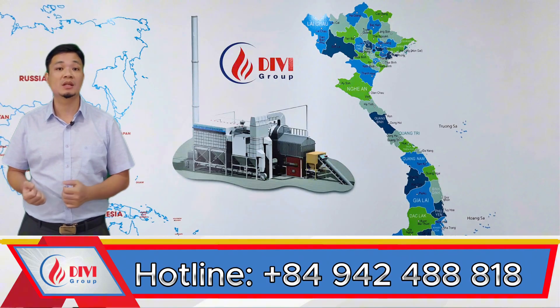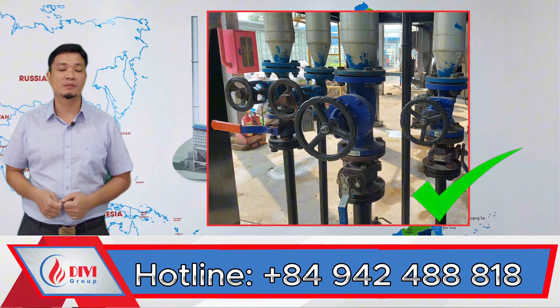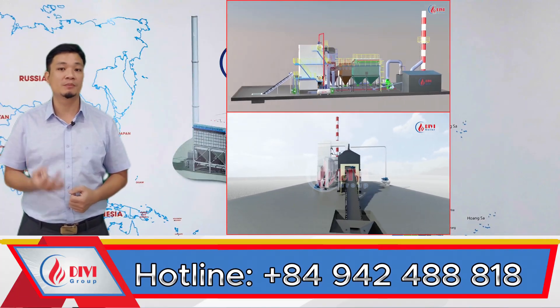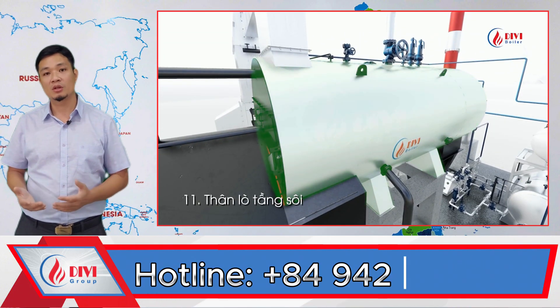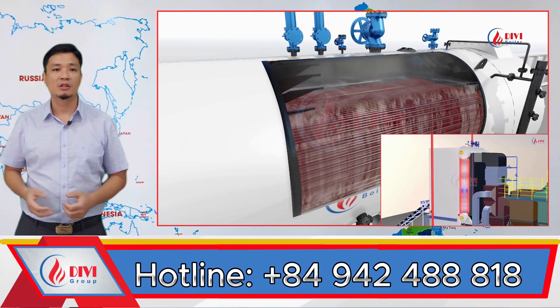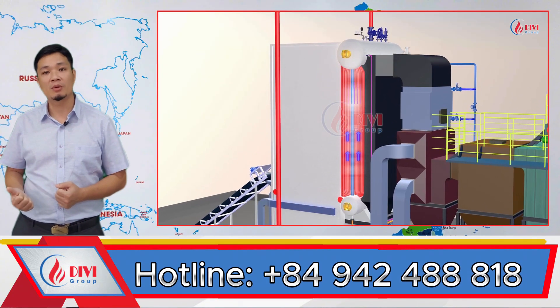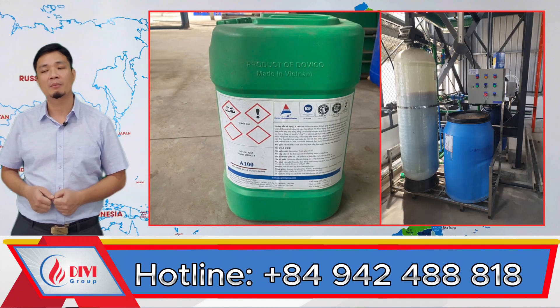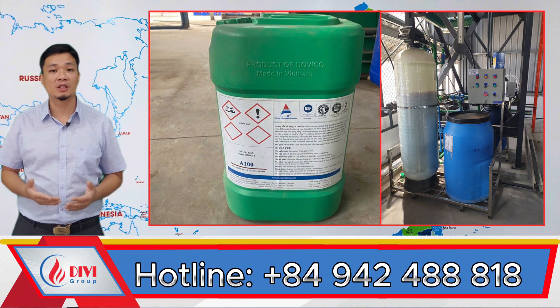But things gradually changed. As the knowledge level of Vietnamese boiler operators improved, people started to understand the importance of proper water treatment and regular blowdown. Thanks to that, scale formation became less of an issue, and the earlier gap between the two boiler types in terms of scale build-up started to close. In the following years, another important issue became more apparent — the difference in steam quality between the two designs. The fire tube boiler, with its large single steam drum, produced much drier steam compared to the two-drum water tube boiler, whose upper drum was smaller. Eventually, ongoing improvements in steam separation internals inside the two-drum boilers, along with proper water treatment chemicals, more optimized feed water systems, and better surface blowdown practices, helped gradually resolve this issue. As a result, the quality of the steam generated by the two boiler types has become increasingly similar, and today the differences in pros and cons between the two designs are no longer significant.